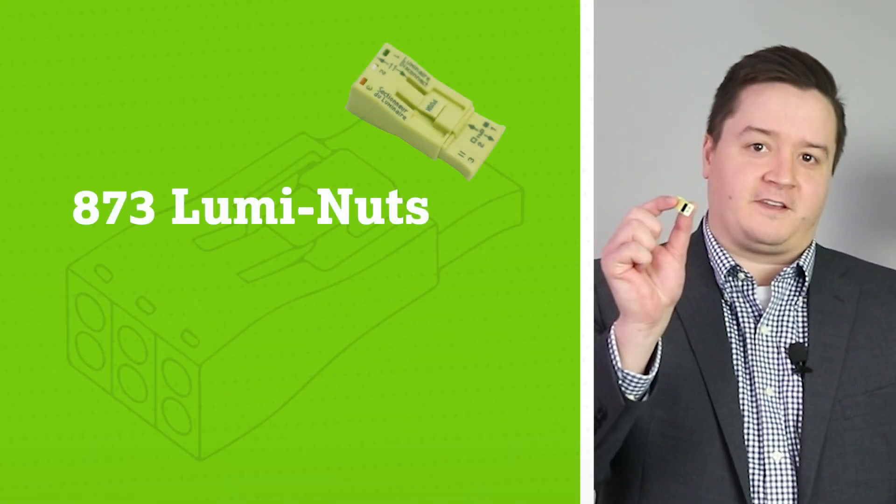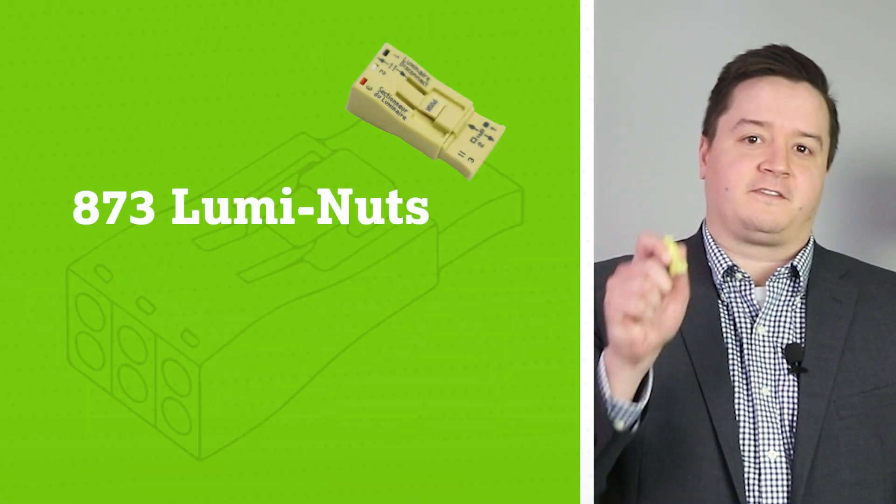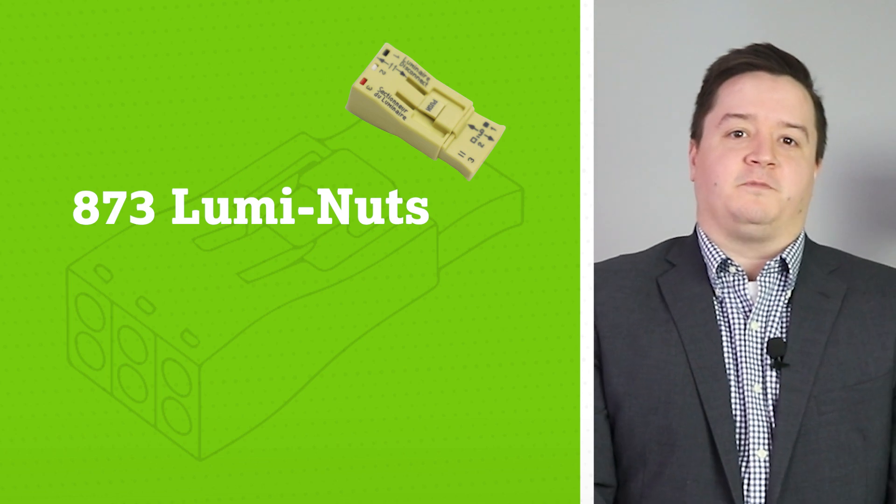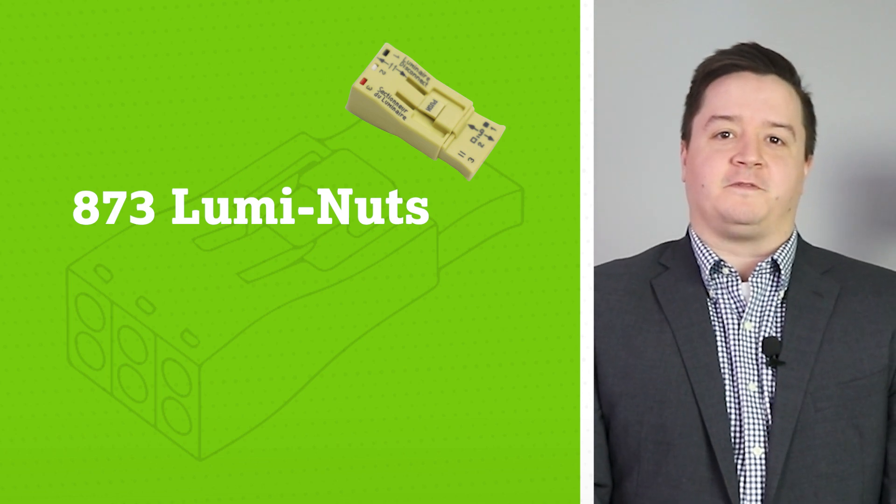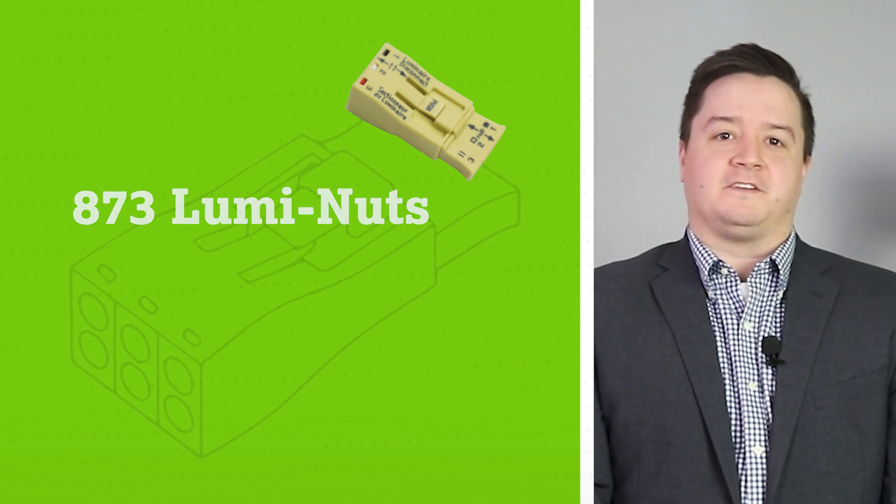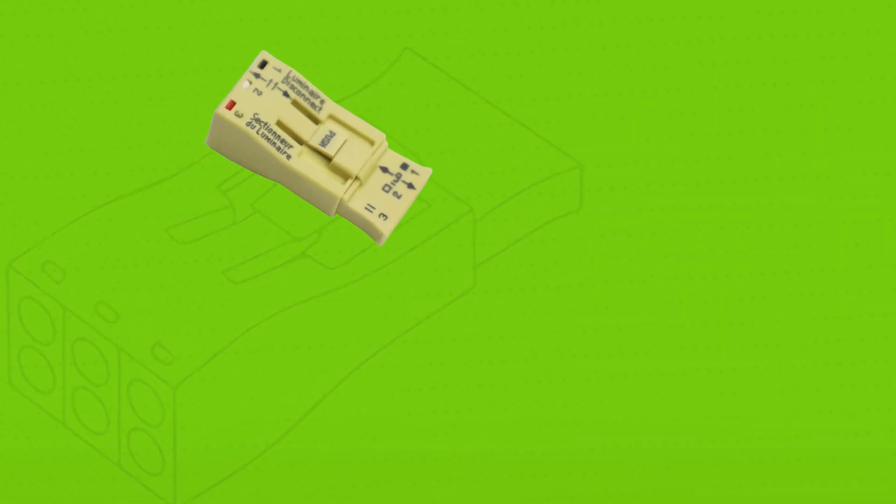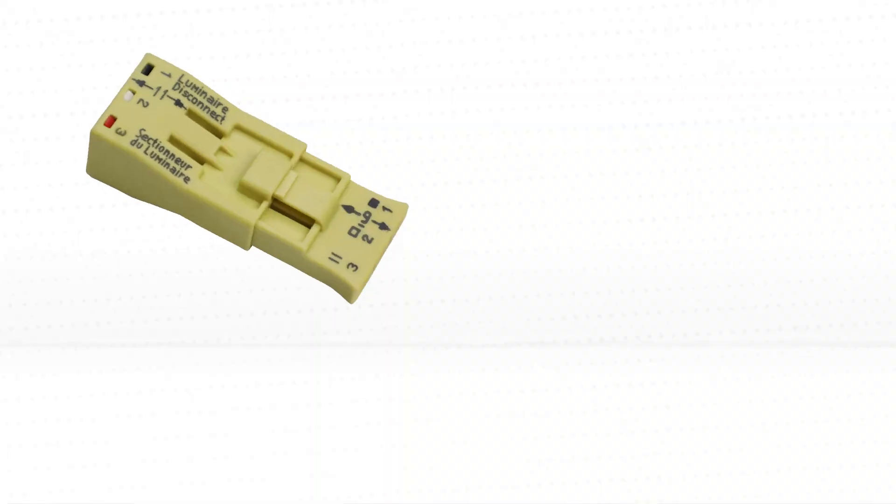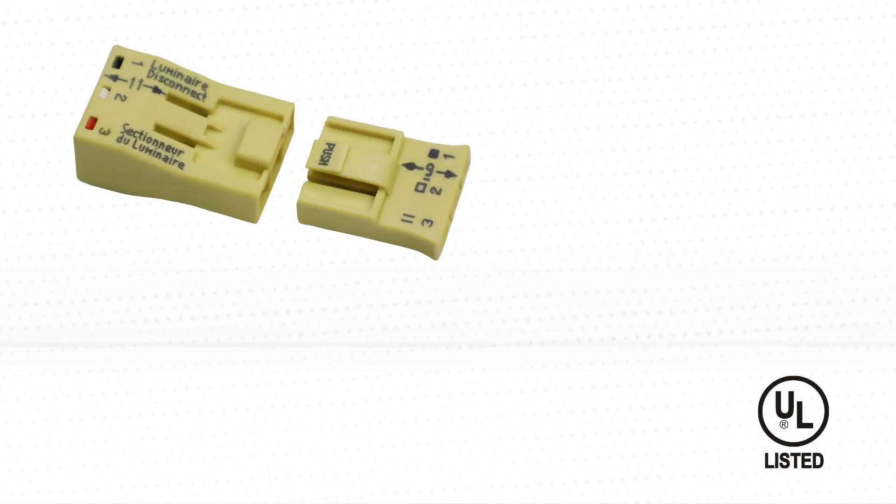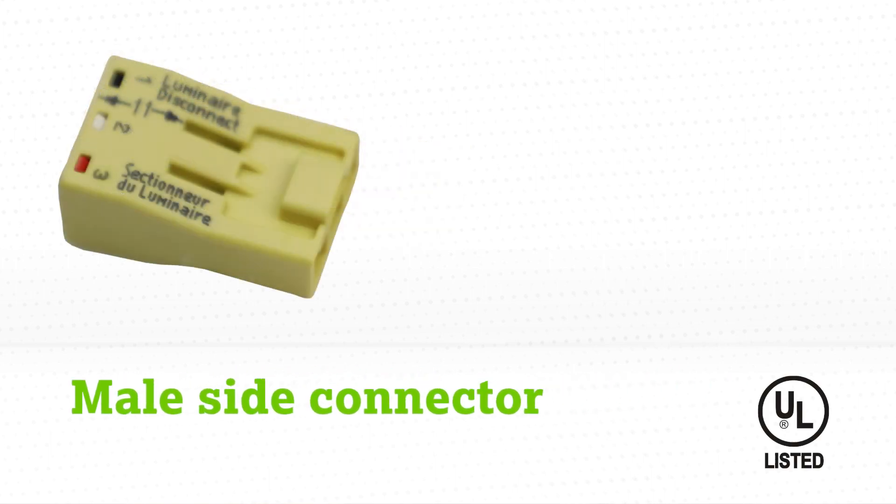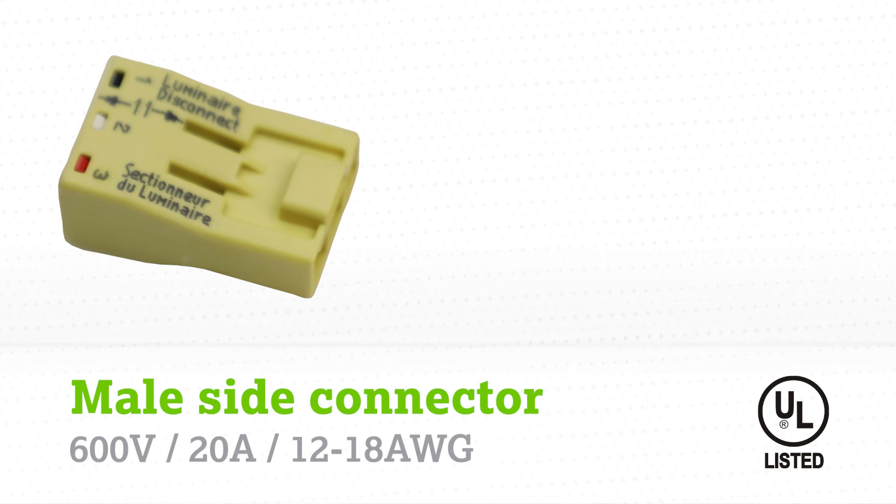Today I'd like to discuss our 873 Series LumiNuts. Our completely touch-proof 873 Series Pushwire Luminaire Disconnects are a UL2459 listed product. The male side connector is rated for 600 volts, 20 amps, and accepts solid and stranded wire ranging from 12 to 18 gauge.